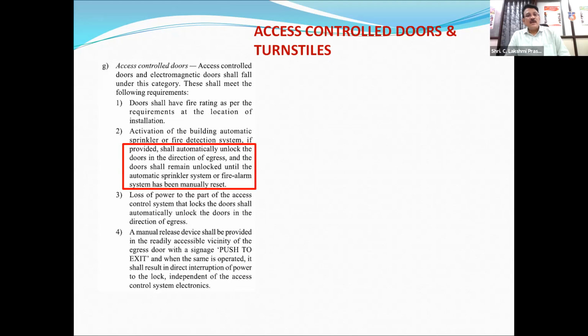So these access control systems shall automatically unlock the doors in the direction of egress, and the door shall remain unlocked until the automatic sprinkler system and/or fire alarm system has been manually reset.